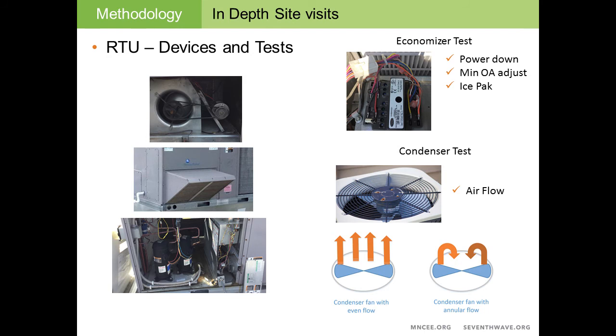We had three main tests that we did on the economizer. The first was a power down test, where we removed power from the rooftop unit to see if the damper moved from a position of minimum to closed, which it should if it would operate normally. We also did a minimum outdoor air adjustment test, where we adjusted the screw on the controls to see if the controller signaled the motor actuator on the economizer to move the economizer damper. And then the last test we did was an ice pack test, where we attempted to trick the RTU into thinking the conditions were right for economizing if they weren't right during the site visit, and see if economizing could happen. So as you can tell from these economizer tests, these are very definitive tests. They either did work or didn't work.